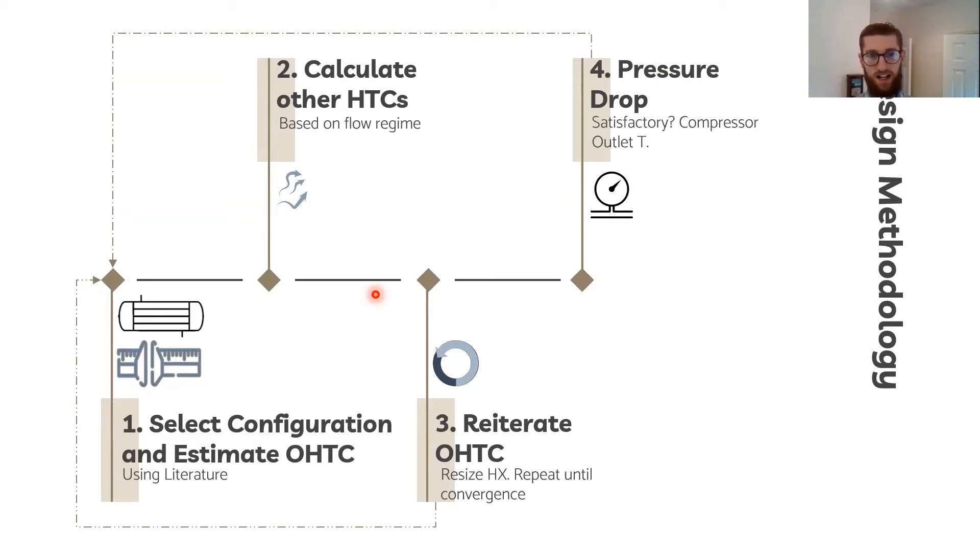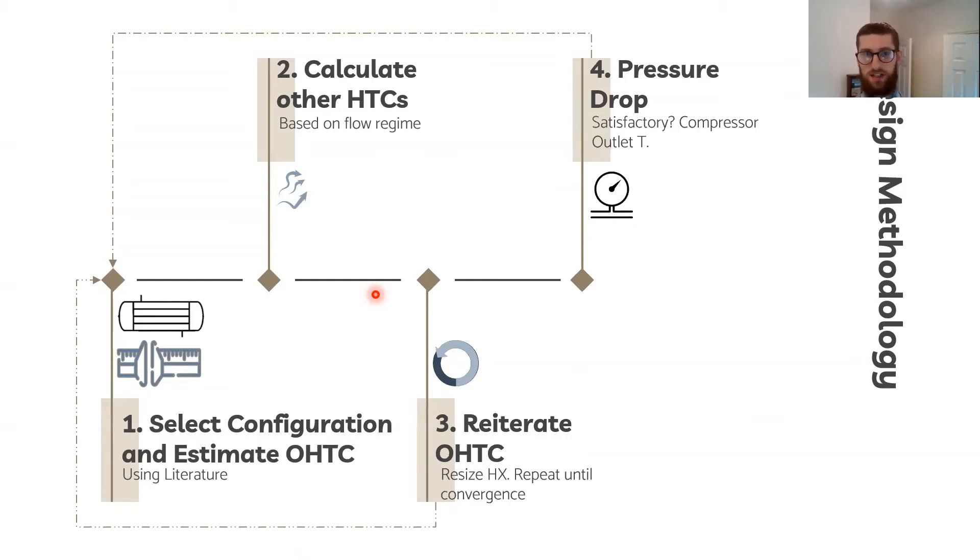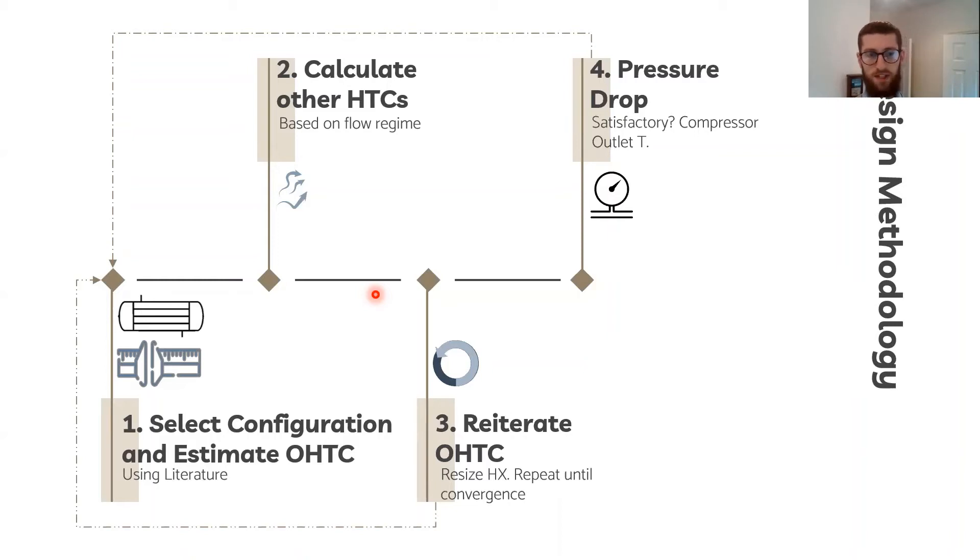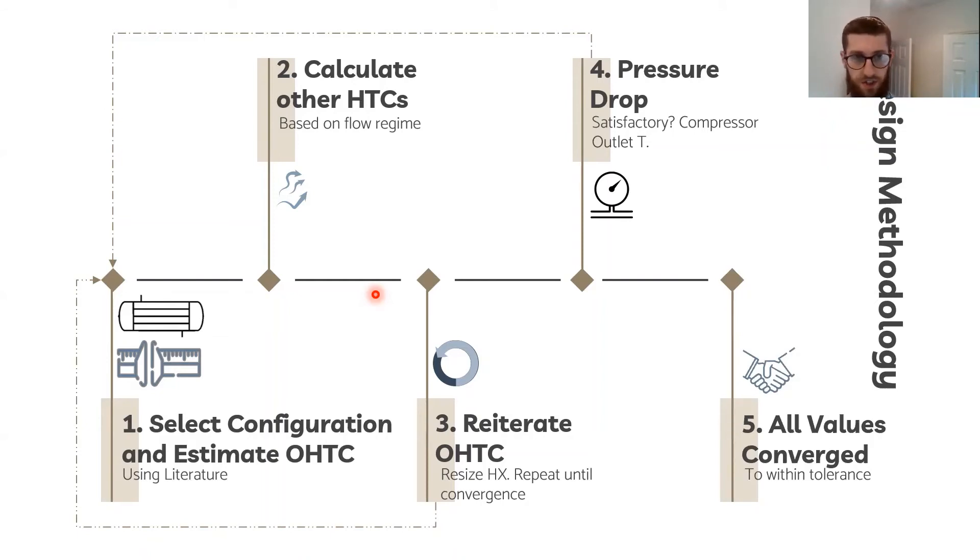I had the added complication that the compressor needs to compensate for any pressure drop in the cooler. So when the compressor outlets at a higher pressure, it also outlets at a higher temperature and that increases the cooling duty, which itself means that the heat exchanger needs to be redesigned. So only once all of those factors converged, and I used an engineering tolerance of about 2%, could the design be accepted.